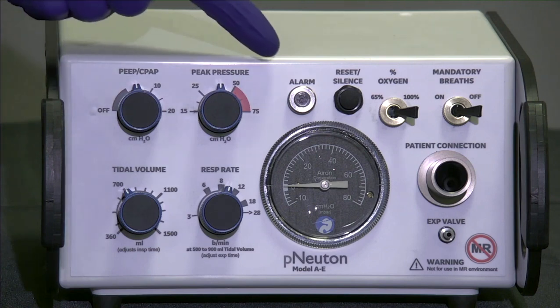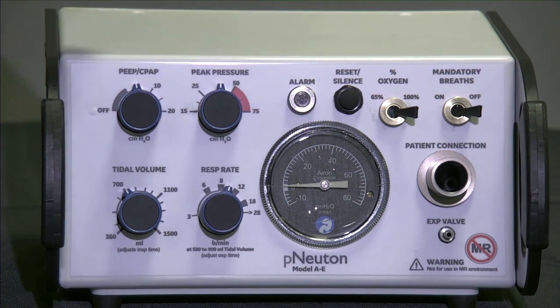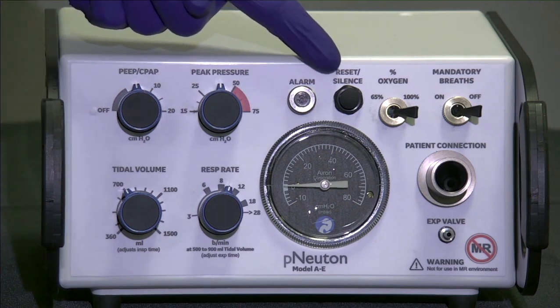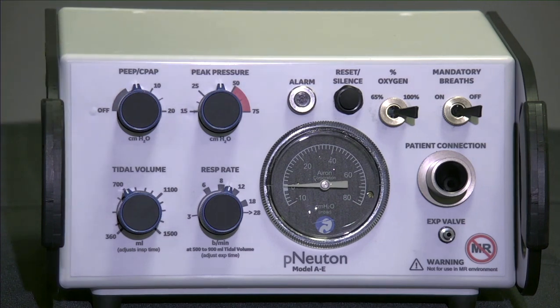Alarm controls. The alarm controls include the alarm visual indicator and the alarm reset silence button. The alarm reset silence button silences the alarm for 1 minute. The alert condition is activated when a patient disconnect has occurred or when low source gas pressure is detected.